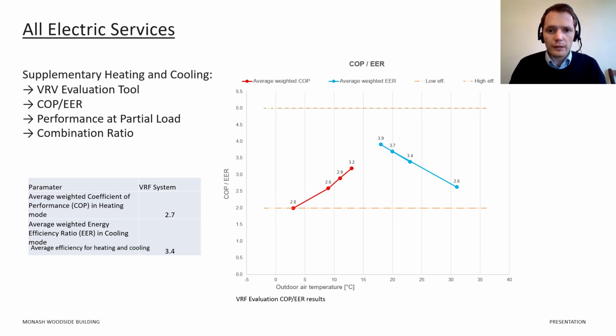To add further complexity, the evaluated system needs to take into account the combination ratio, which gives the VRF plant the ability to add additional indoor units to each set of condensing units. Generally speaking, the system has made allowance for an additional 20% of heating and cooling load to meet the building's future needs. Based on the selection received from the suppliers, the capacity tables in both heating and cooling mode were used to obtain the input power and the associated available heating and cooling capacities. These design values and test points below and above them were used to determine the coefficient of performance in heating mode and the energy efficiency ratio in cooling mode. The result is a neat little linear graph telling us that in heating mode the average weighted COP at approximately 10 degrees Celsius is 2.7 and the average weighted EER is 3.4 at approximately 23 degrees Celsius. These values were then populated into the PHPP to accurately determine the PER demand.